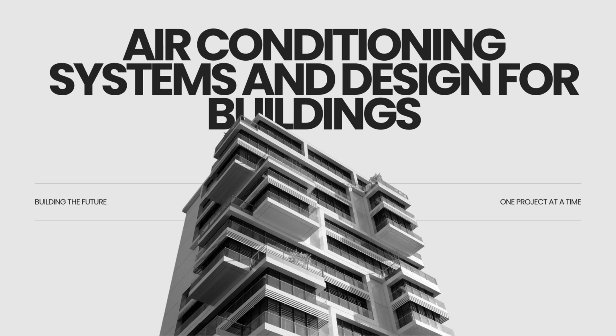Okay, let's apply this TR-based sizing to a commercial setting. The source gives a sample project, a commercial bank, with a floor area of 110 square meters. It assumes an area per TR of 20 SQM for a bank, which falls right within that 20 to 25 SQM TR range we just saw in Table 3. How do we calculate the aircon requirement here, and what are the practical implications of the different options from the catalog?